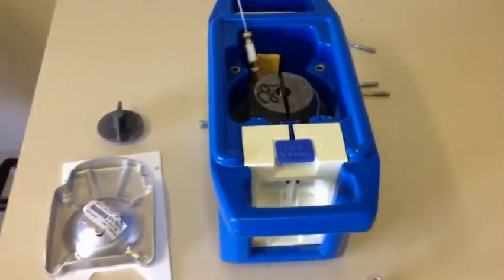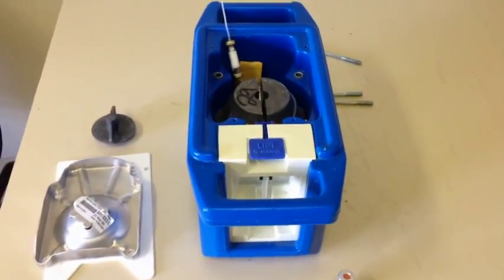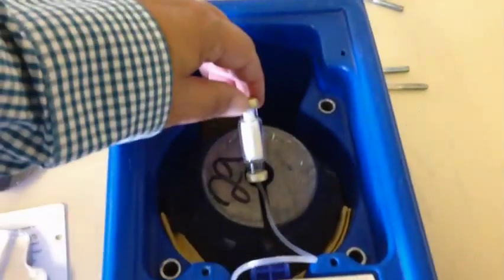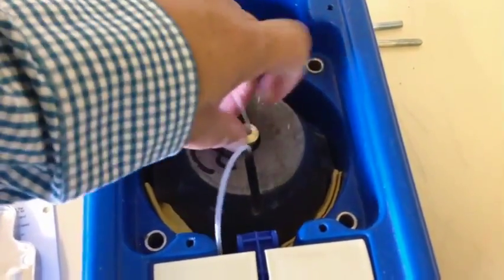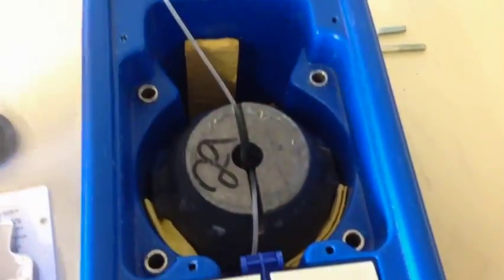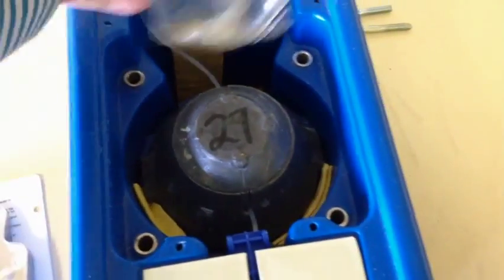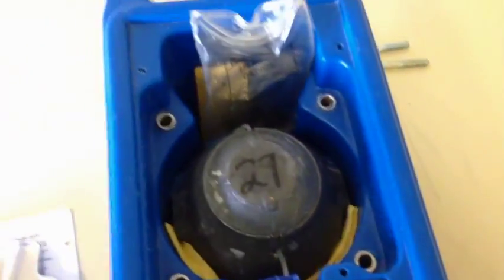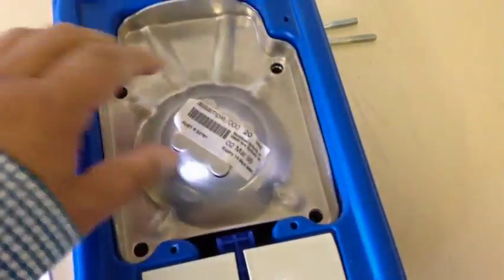The principle is very similar and it's a fairly simple system. When these are loaded, you'd want to load them as quickly as possible to reduce staff radiation. From time to time we used to find there'd be a kink in the system—either as it gets poked in or as the lead cap gets put on, you can end up with a kink in the line that stops it from being eluted. But generally they're tested a few times before they come out to the department, and we don't have too many problems with that.